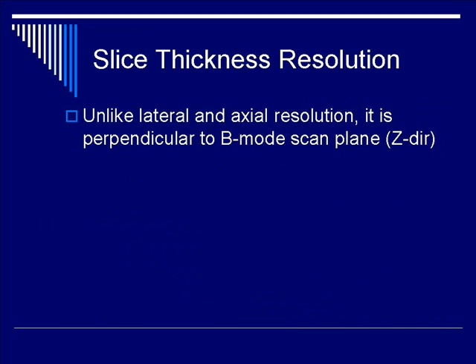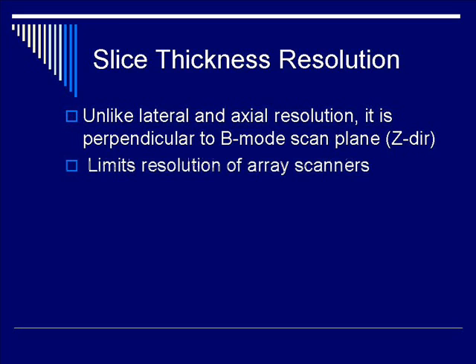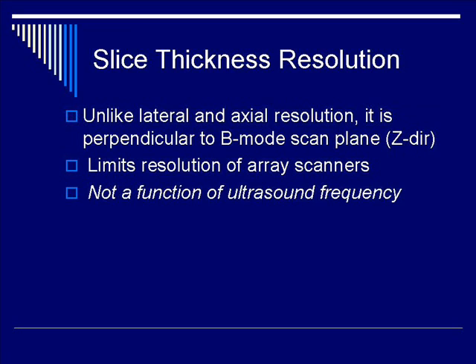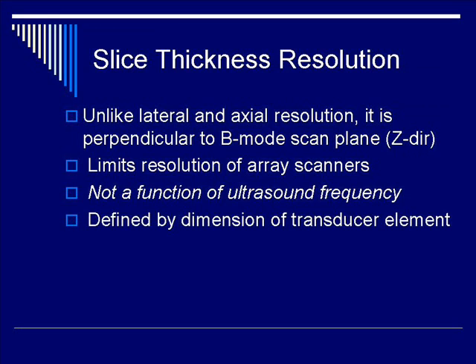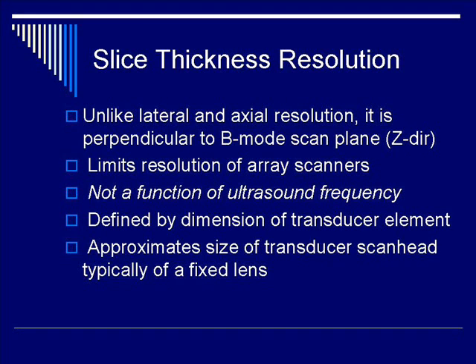Unlike the lateral and axial resolution, slice-thickness is in the z-direction, which is perpendicular to the B-mode scan plane. It limits the resolution of the array of scanners. However, it is not a function of ultrasound frequency, as is the case for lateral and axial resolutions. Rather, it is defined by the dimension of the transducer element, which is most often the size of the transducer scan head, formed typically with a fixed lens.